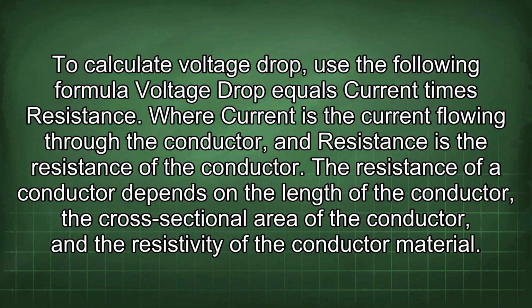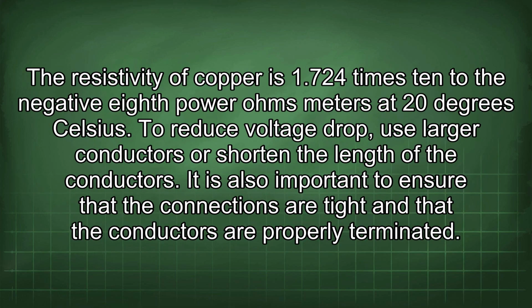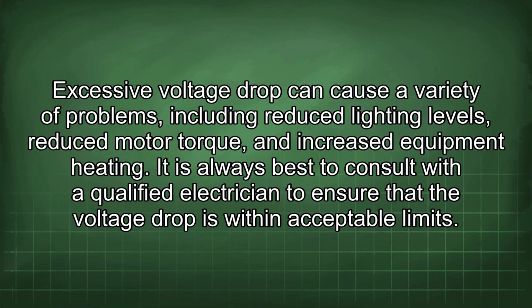The resistance of a conductor depends on the length of the conductor, the cross-sectional area of the conductor, and the resistivity of the conductor material. The resistivity of copper is 1.724 times 10 to the negative 8th power ohm-meters at 20 degrees Celsius. To reduce voltage drop, use larger conductors or shorten the length of the conductors. It is also important to ensure that the connections are tight and that the conductors are properly terminated. Excessive voltage drop can cause a variety of problems, including reduced lighting levels, reduced motor torque, and increased equipment heating. It is always best to consult with a qualified electrician to ensure that the voltage drop is within acceptable limits.